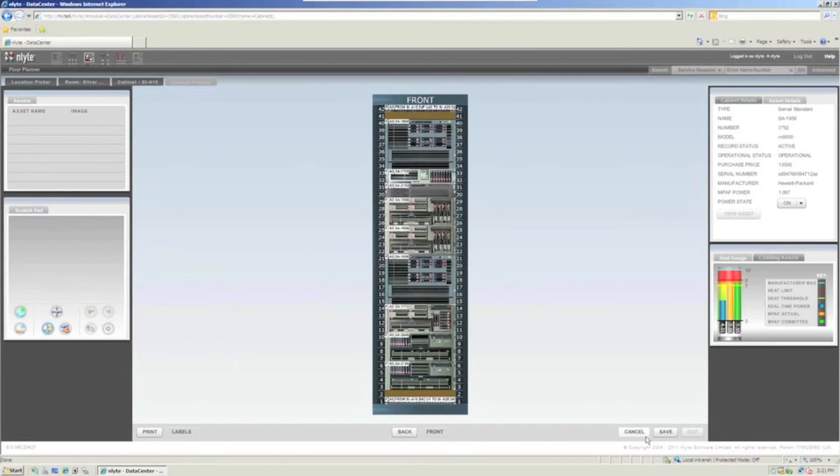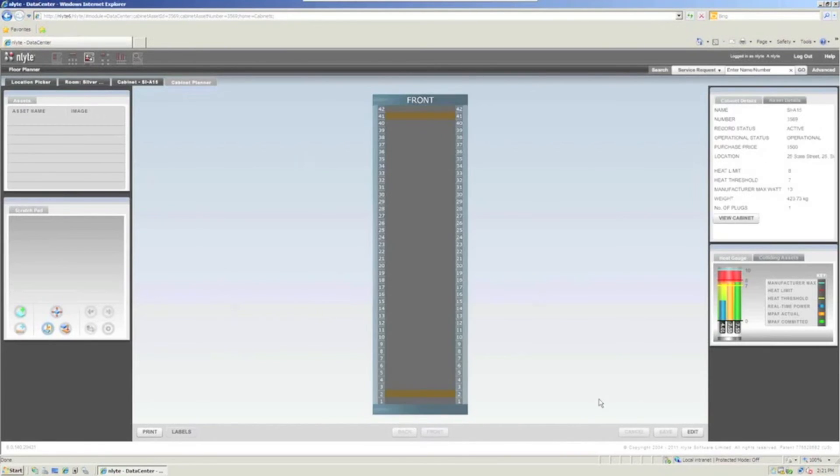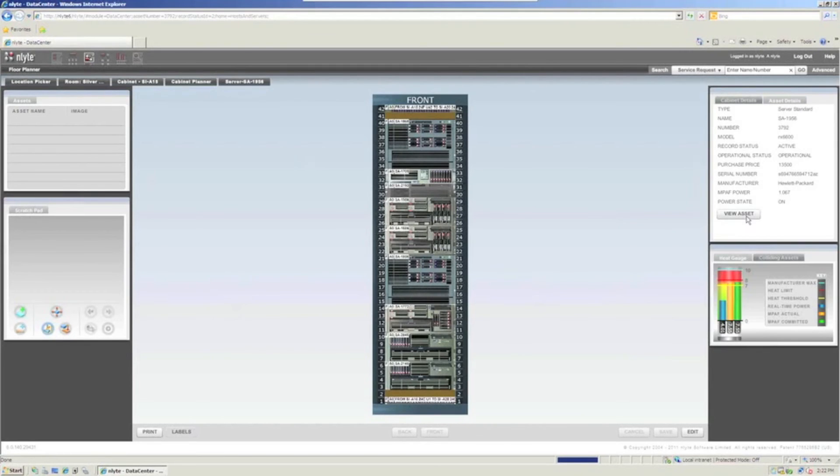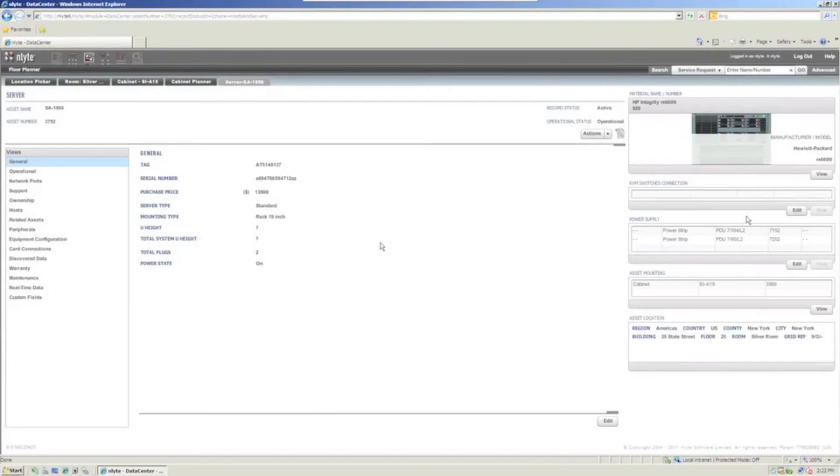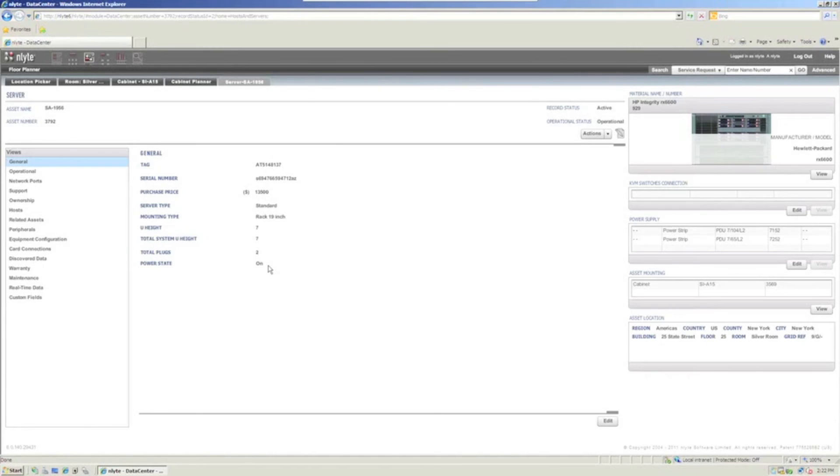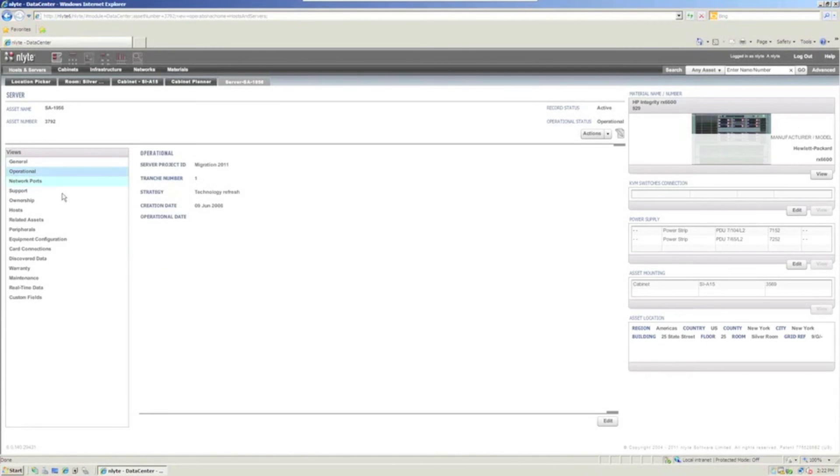And you can see that that would certainly lower my power consumption down under what my threshold of seven was. So maybe that's a good idea. Maybe I ought to see if I could find another home for that. Or I could try a different cabinet here and let you go through there. So lots of different ways you could do that. So let's actually take a look at this particular server and see if we can find somewhere that we might want to put that. So if I look at that particular asset, it's a standard server. Let's view that asset and understand what all we're tracking in nlyte. So this is a RX 6600 from HP. Again, we bring in the picture and all of the manufacturer's specifications about it. I know that it's a standard 19-inch rack. I know that this particular server is taking up seven U of that rack that we've got out there. I can see that this particular server requires two different plugs.